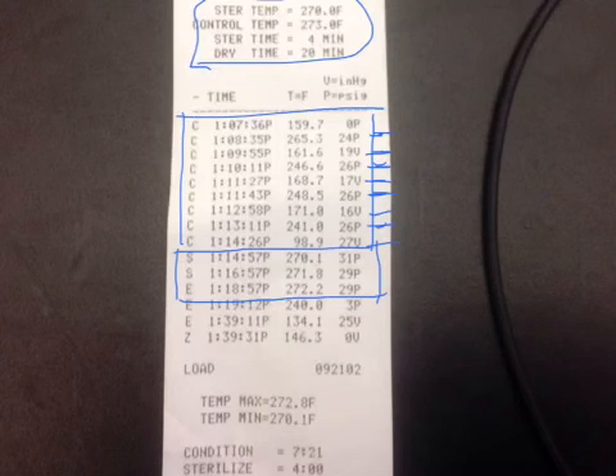This occurs at 114.57, and then it stays in range until 118.57. So this is your 4 minute sterilization time in this prevac. We can look at our four columns. In column one, we see that the time meets the parameter. Column two, we'll go down column two and see that it is above temperature, above 270 degrees. And then column three, we can see that it's above 27 psi. And so this 4 minute cycle was complete.